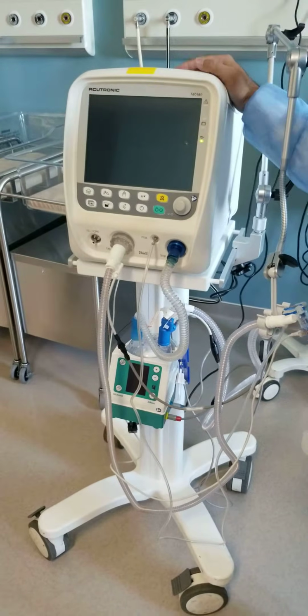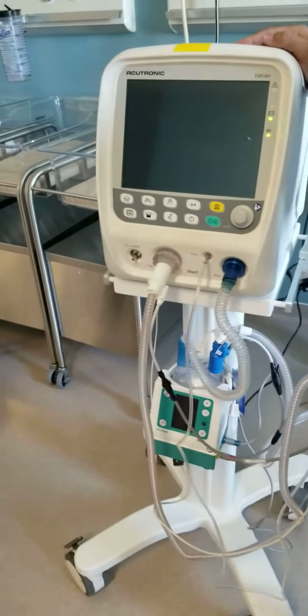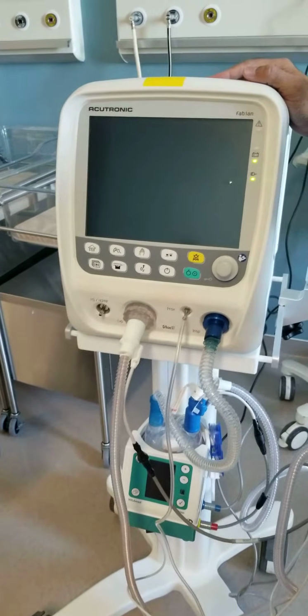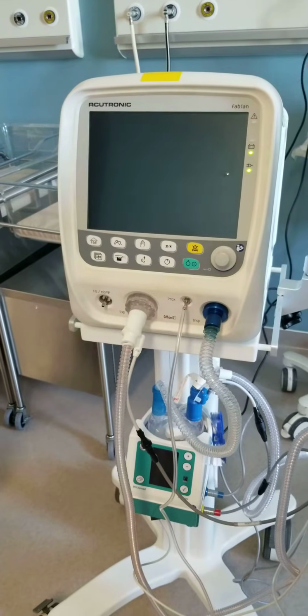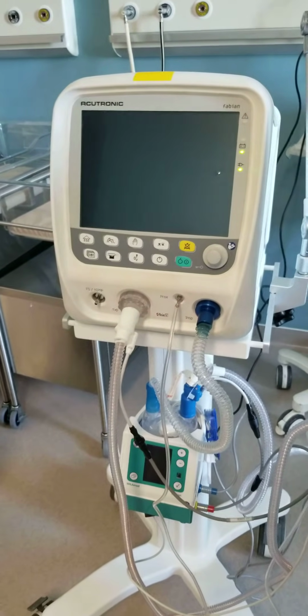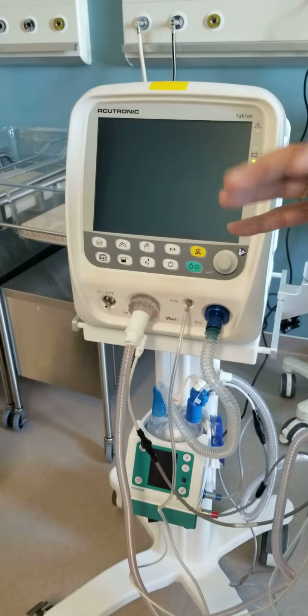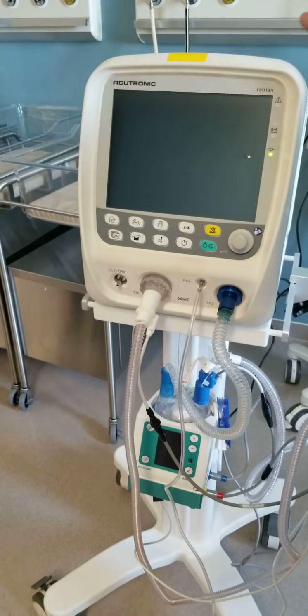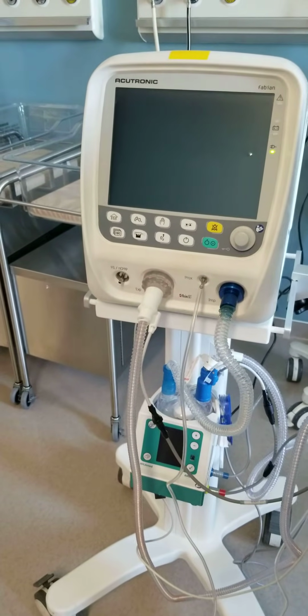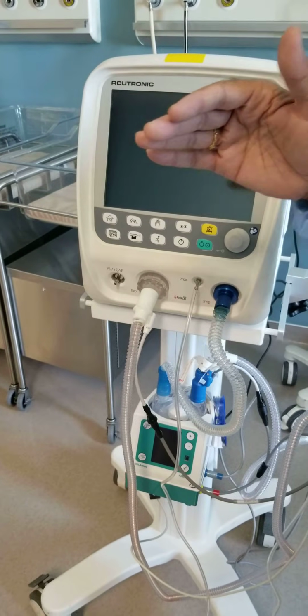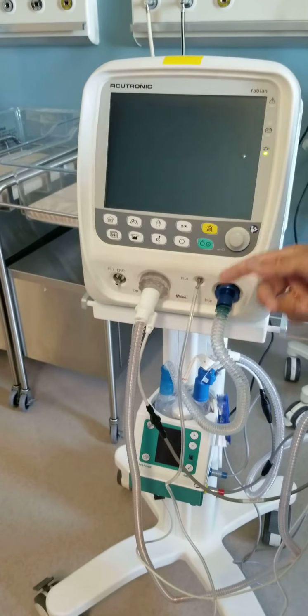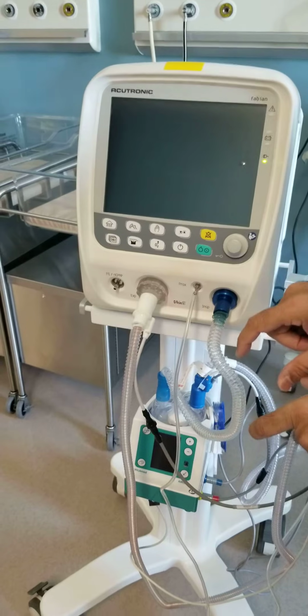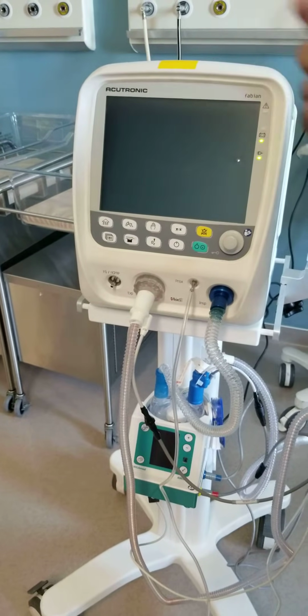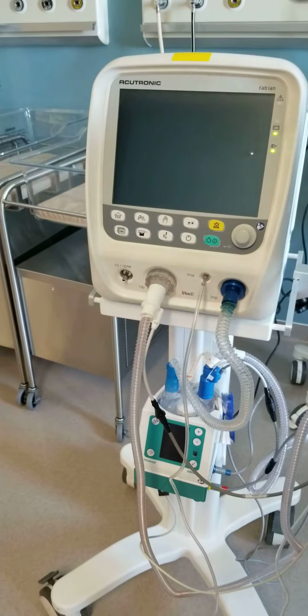So this is the Fabian HFO from Acutronic. The main machine as it is, the ventilator is designed to handle all babies starting from 300 grams up till 30 kgs of pediatric. So you have a dedicated neonatal mode where you can handle babies till 10 kgs and a pediatric mode in the same, because you will be just changing the flow sensor in the circuit. You can go up till 30 kgs. It's a 4-in-1 ventilator.